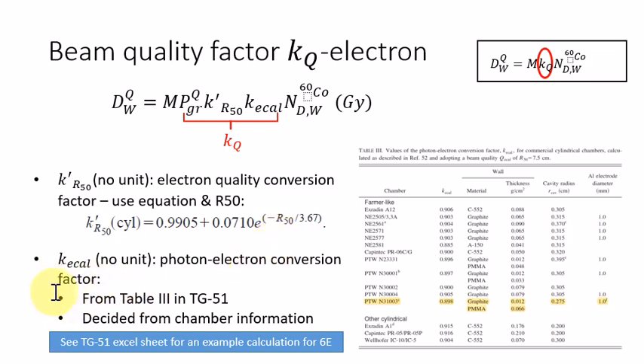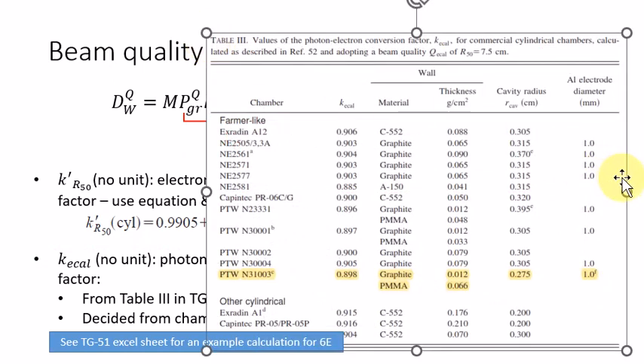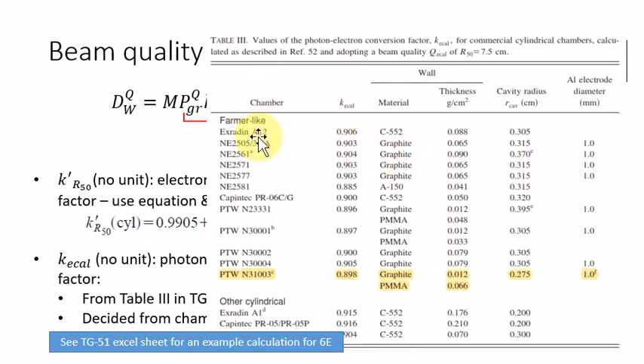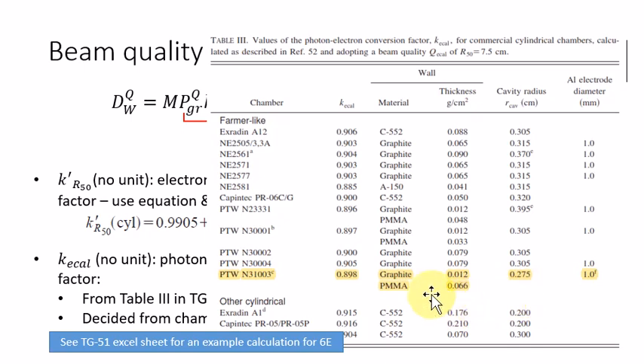The last factor, which also has no unit, is the KECAL — the photon-electron conversion factor. We can find this factor from Table 3 in the TG51 report, and it is determined from the chamber information. It lists the types of chambers normally used for TG51 measurements and the KECAL value for each. If your chamber is not listed, find the closest match by thickness, cavity radius, and material, and obtain your KECAL from that entry.